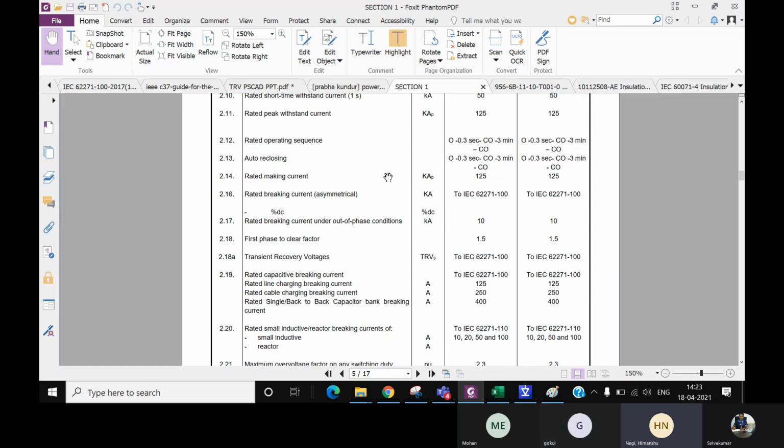I think it's because of maybe British standard. Correct, because of IEC. It's the same thing. IEEE calls this the earth fault factor. In IEC 62271 we call it the first pole to clear factor.